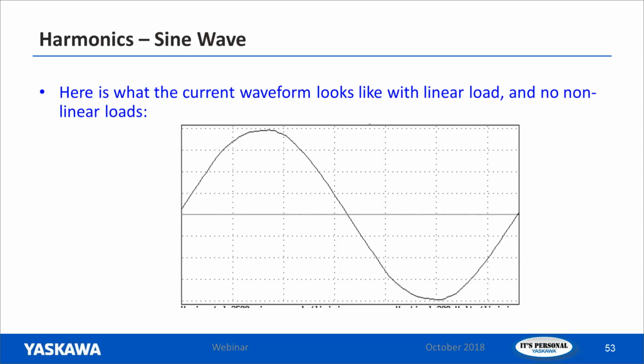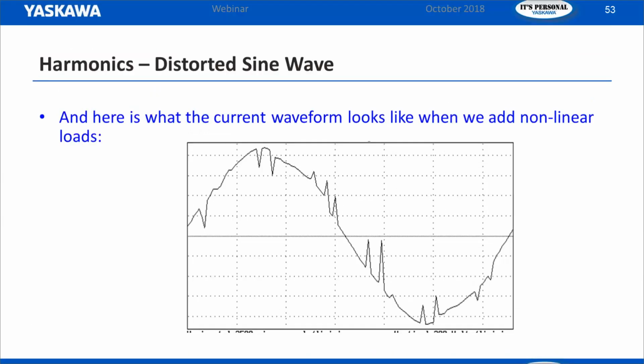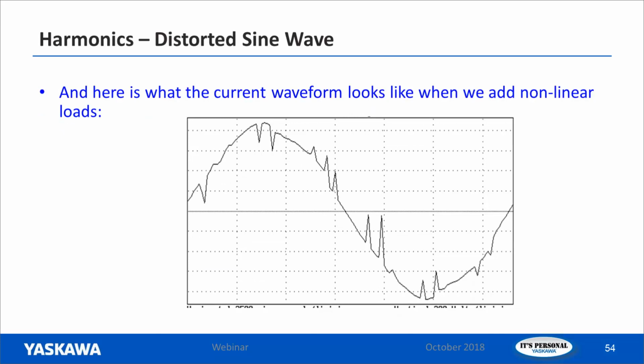You know what, before we look at that, we're going to look at this. This is what the current waveform looks like with a linear load, and a linear load is going to be just a three-phase AC motor drawing power right from the line. This is what your current waveform is going to look like. It's a nice, beautiful sine wave. But if we put a VFD in between the line voltage and that motor, and we run the motor, now our sine wave of current heading into the VFD is going to look like this.